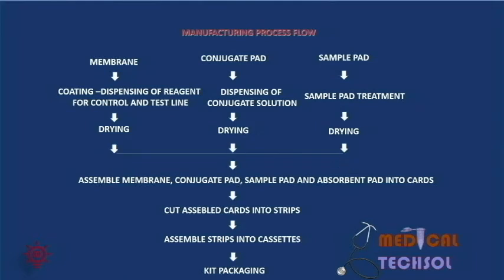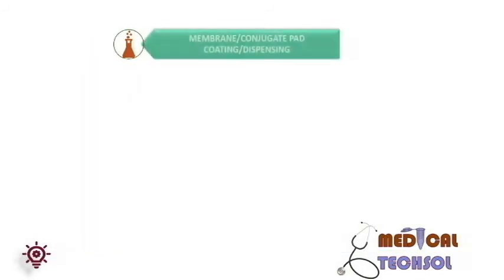The manufacturing flowchart proceeds as follows: the first step involves coating, dispensing, and treatment of the membrane, conjugate pad, and sample pad. The second step is drying of these components. The third step is assembling or lamination, and the fourth step is cutting into strips. The fifth step is cassette assembling, and the last step is kit packaging. The instruments used in this process will be explained in the next section.